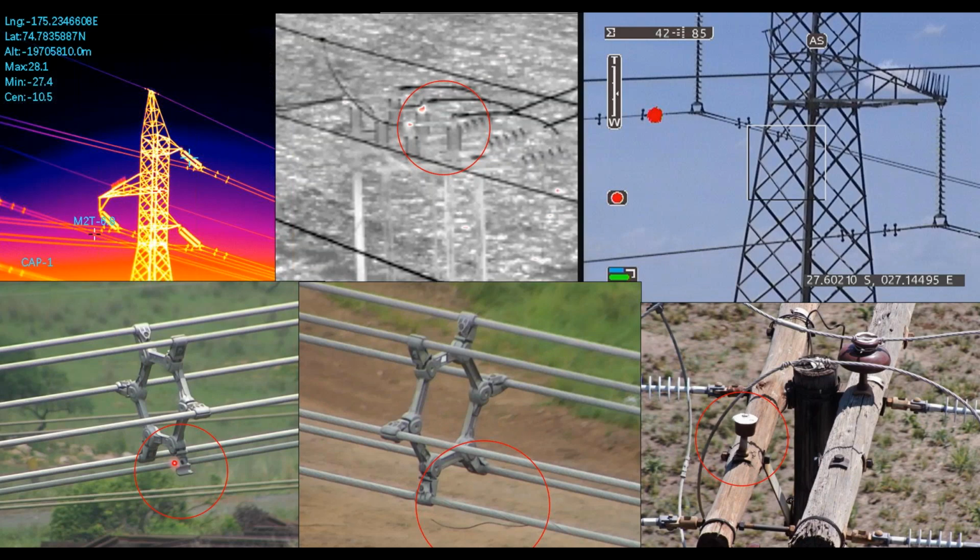Like you can see the spacers, some of them are already loose, which may cause issues going forward. And the over-talking as well, you can see the breaking conductor strands, and this can lead to breaking of these conductors. We may almost take the whole bundle down if this continues. Those are the sort of issues you will pick up with these drones, which you wouldn't see from the ground or even from a helicopter. It's very difficult to see this sometimes because you fly from a very high angle.